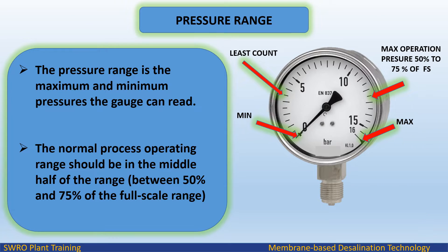Pressure Range: The pressure range is the maximum and minimum pressures the gauge can read. The normal process operating range should be in the middle half of the range, between 50% and 75% of the full scale range.